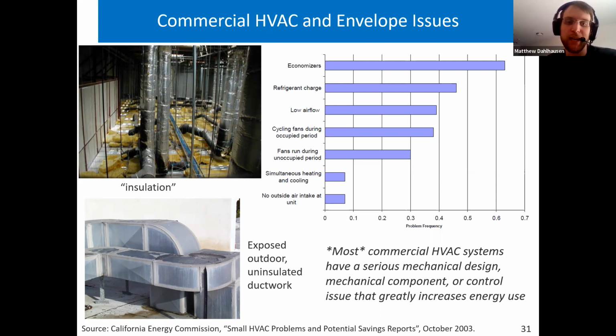These images are from a California Energy Commission study that was looking at problems in small rooftop HVAC systems. They found that the HVAC systems themselves have a lot of issues, especially economizers. Economizers are a device that opens the outdoor air damper to provide 100% outdoor ventilation air when the air is cold enough to provide cooling. Economizers routinely break, with around half of economizers having some serious control issue, such as the dampers being stuck open or closed, or the temperature set points set incorrectly.